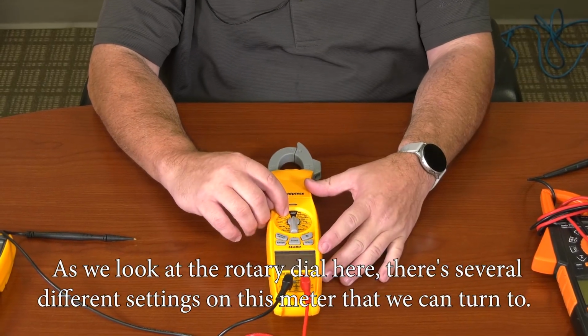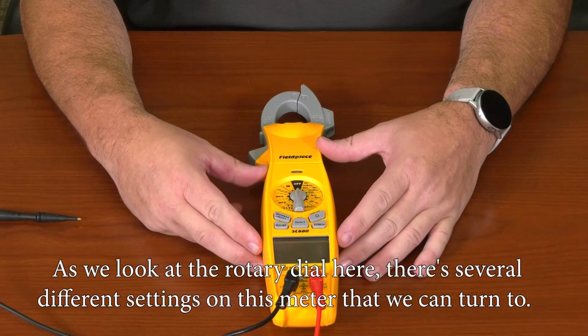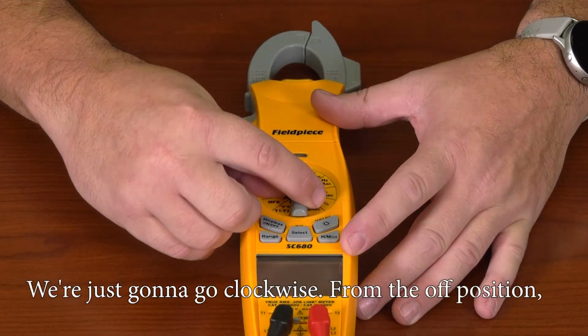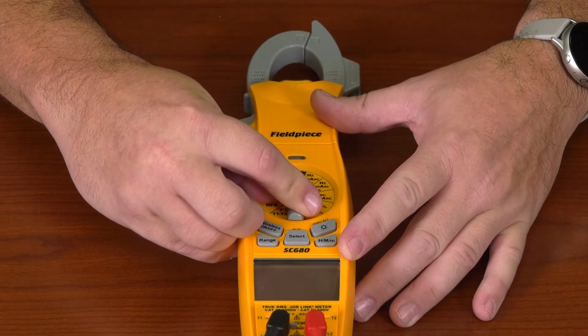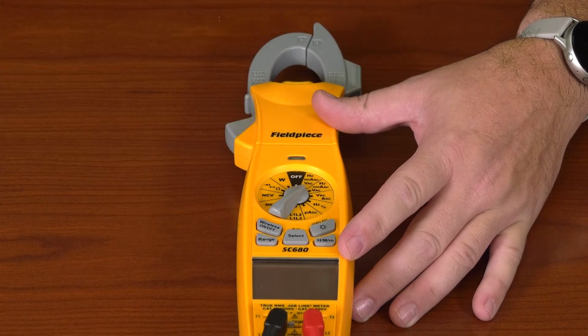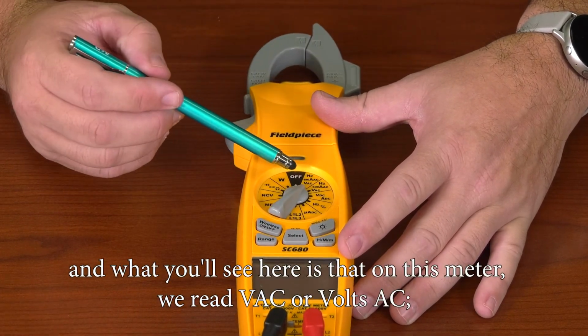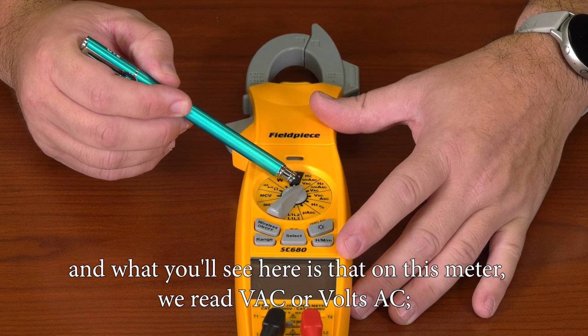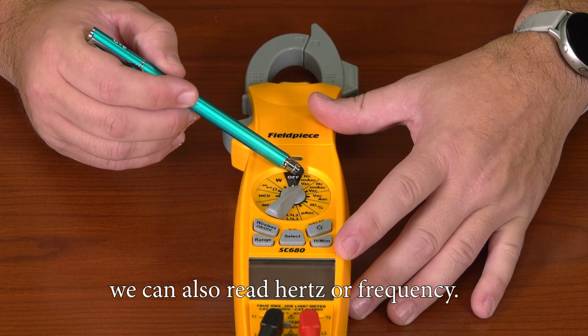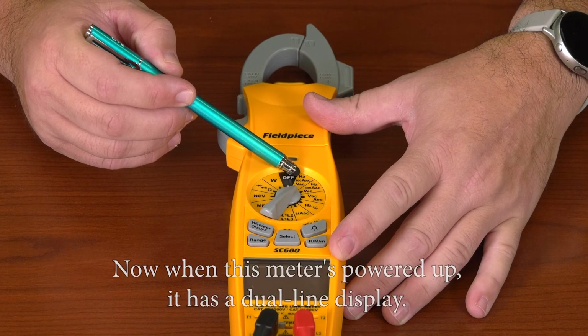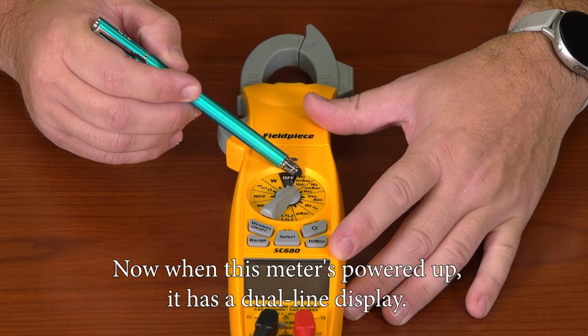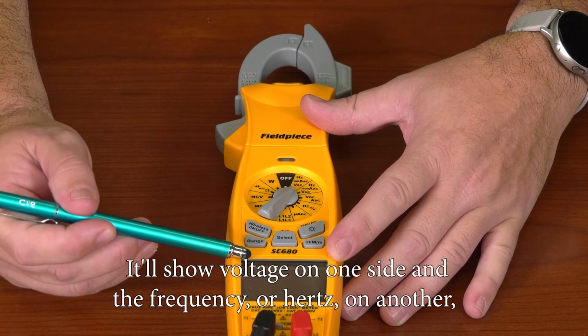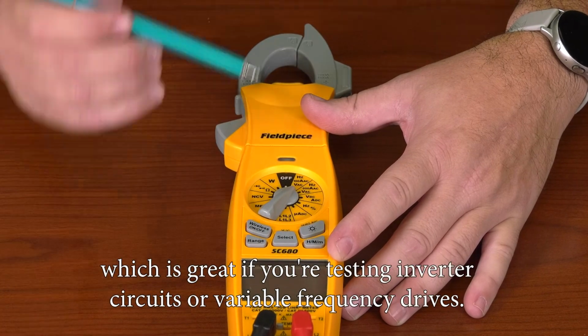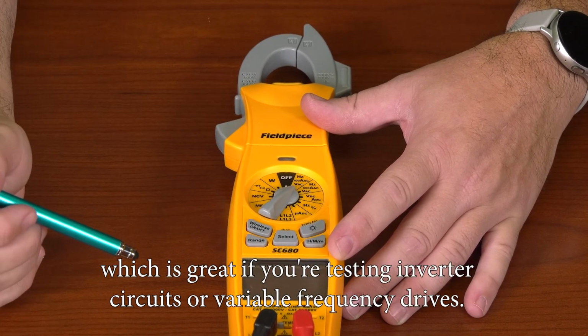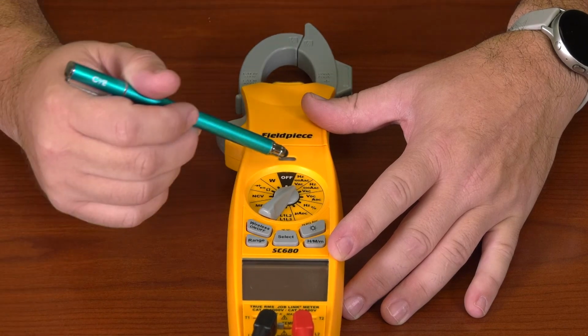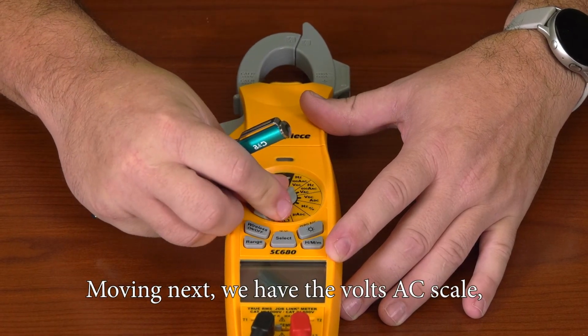As we look at the rotary dial here, there's several different settings on this meter that we can turn to. We're just going to go clockwise. From the off position, we're going to go to the left. And what you'll see here is that on this meter, we read VAC or volts AC. We can also read hertz or frequency. Now, when this meter is powered up, it has a dual line display. It'll show voltage on one side and the frequency or hertz on another, which is great for testing inverter circuits or variable frequency drives. Moving next, we have the volts AC scale.